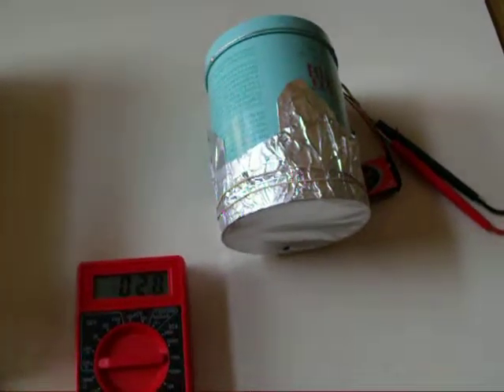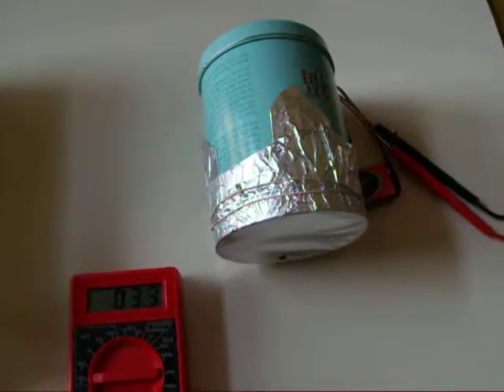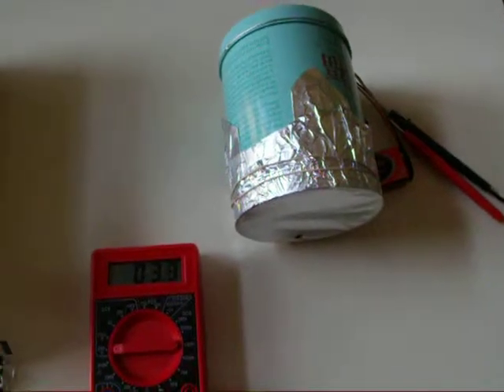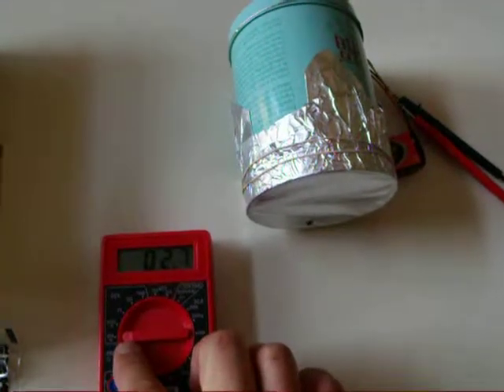So here we are, we've assembled and zeroed the ion chamber to where we'd like it to be. I have the meter in the 200 millivolt range.